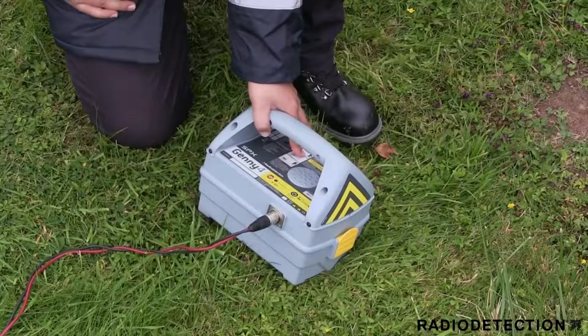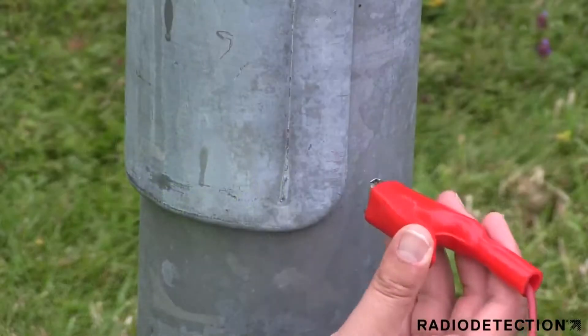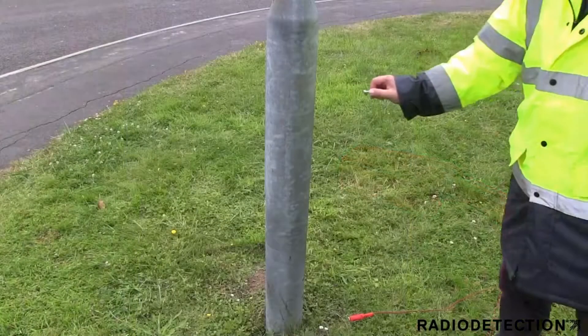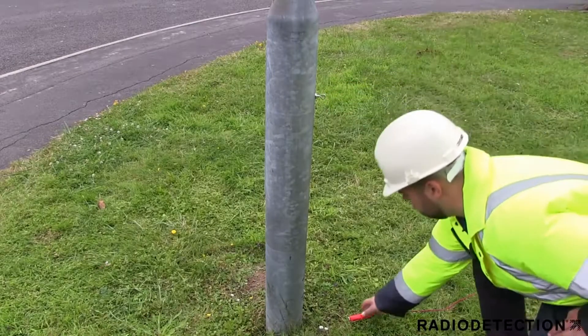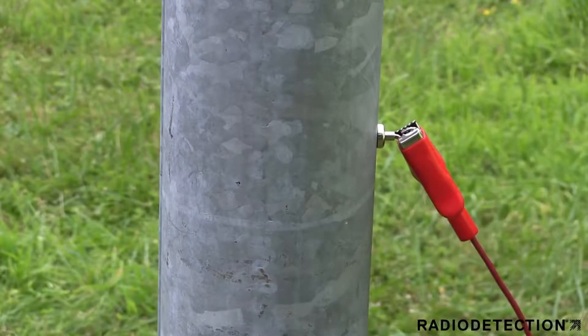For your own safety, do not turn on the Genny until you are ready to apply the signal. The direct connection lead's red clip can be attached to a metal conductor such as a street light. If you cannot use the direct connection lead to clip directly to the street light, use the magnet accessory in an area where metal is visible. This will help the Genny signal couple to the street light.